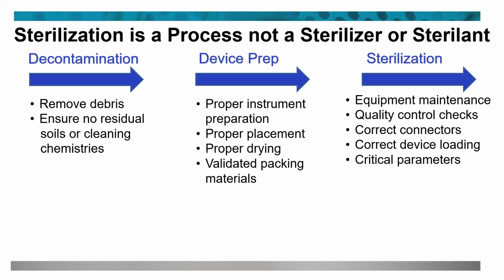The cleaning and sterilization process is complex for these systems. Items must be thoroughly cleaned during the decontamination process, as you guys have heard many times. If we don't clean it, we can't sterilize it. So we need to make sure that it's clean and any residual chemistry is removed, because that may interfere with the sterilization process too.